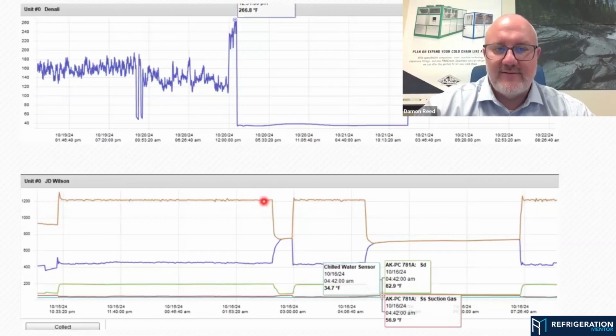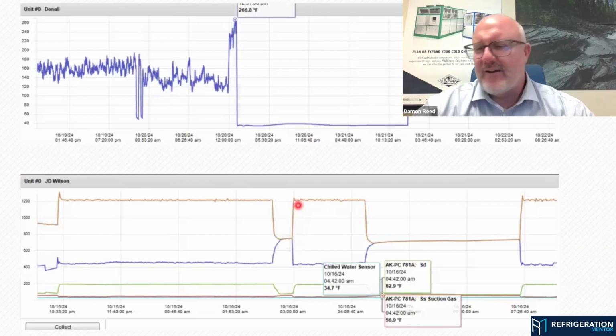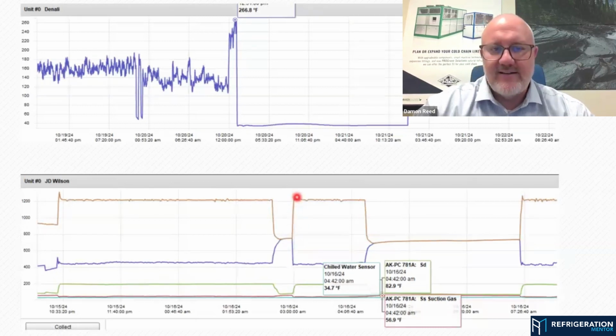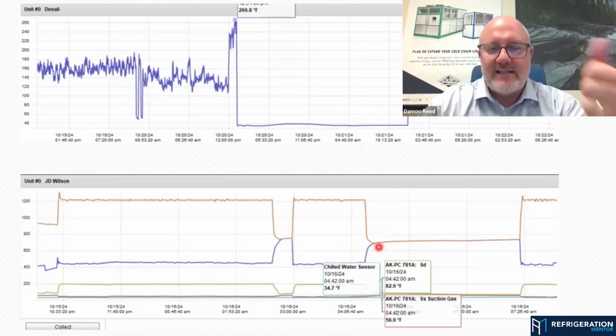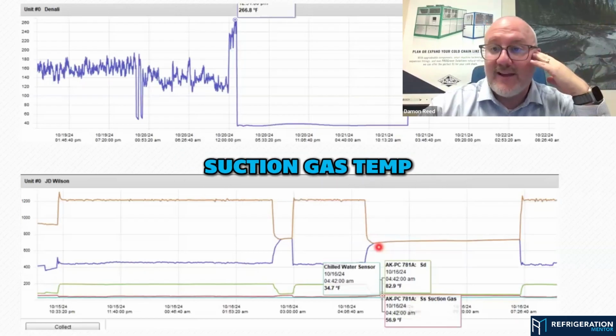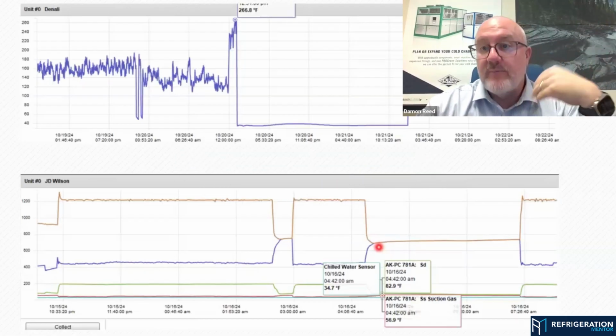We operate, everything was looking perfectly normal. And then all of a sudden, boom, we trip. Now we're off. Now things have equalized. Guy goes out, resets it again. Everything's running normal. Boom, it trips again for no particular reason. I mean, we're looking at discharge temp. We're looking at the chilled water sensor. We're looking at suction gas temp. So then, that's where we make the call.